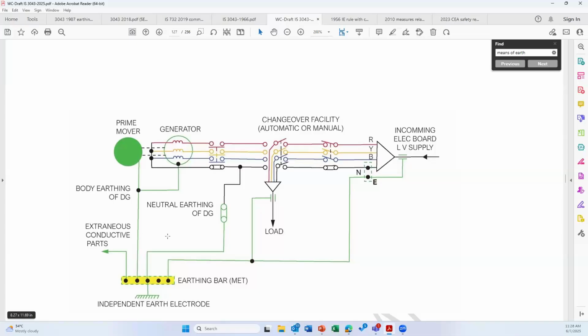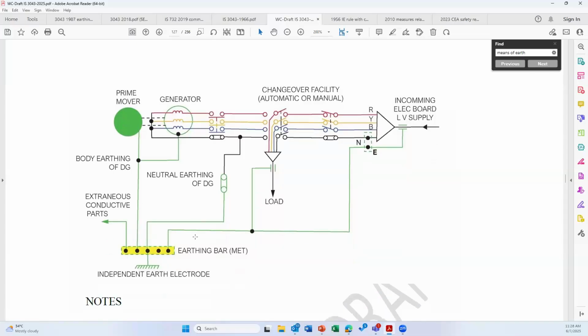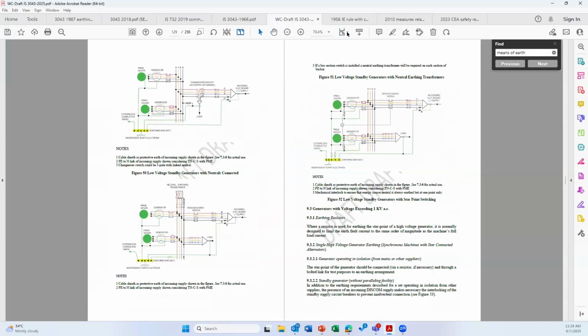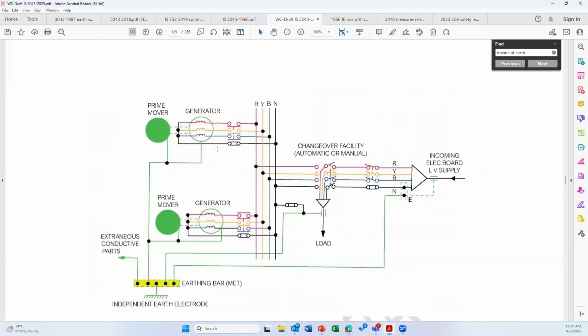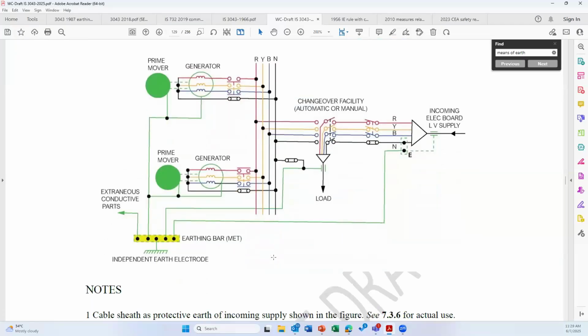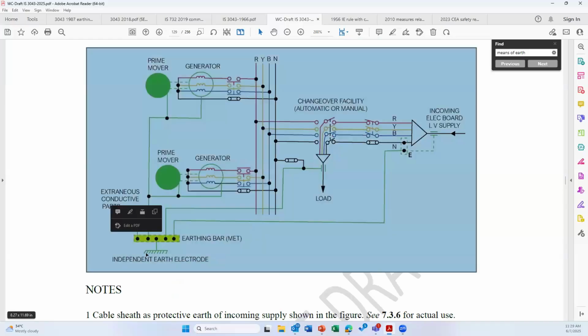But even with this picture, the practice of earthing for a DG, with two separate pits for neutrals and two separate pits for body, was followed, which was absolutely wrong. This picture is the correct way of earthing a generator. The next picture, if you have multiple sources, multiple DGs, explains how to do it. There are three options here. Please note that everywhere the connections are made to a common earth bus bar, never to the earth pit, the common earth bus bar.